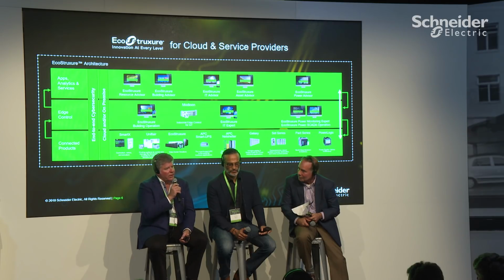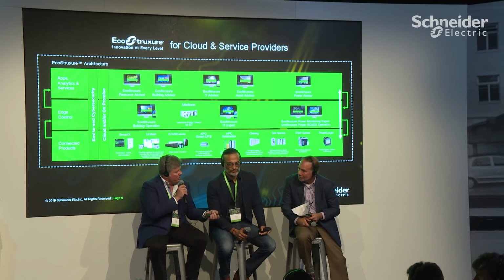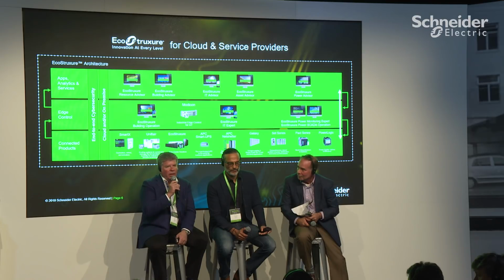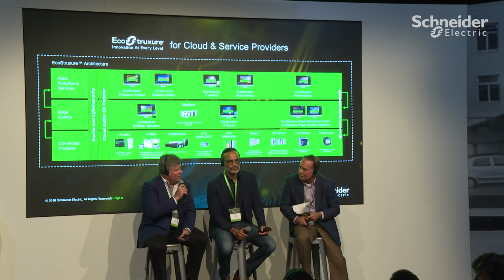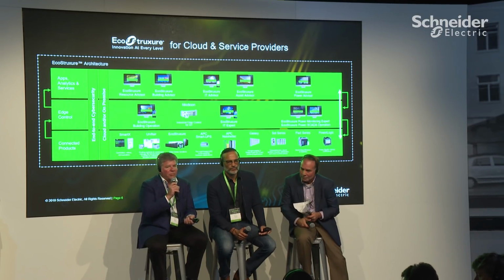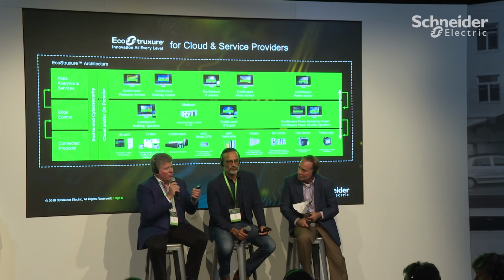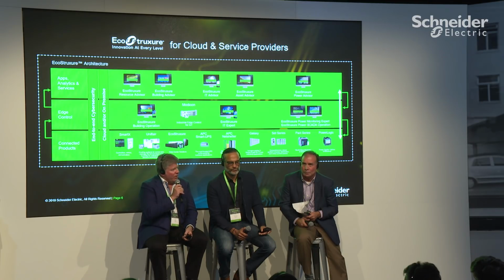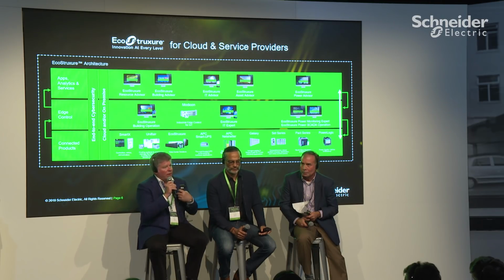When you're using a water side or air side economized cooling solution, changes in humidity and temperature have a dramatic impact on cooling. Typically, after a data center is commissioned and tested to operate within its designed curves, operators leave those set points and only go back to change them when something breaks. But that's a really inefficient way of operating a data center, especially at large scale.